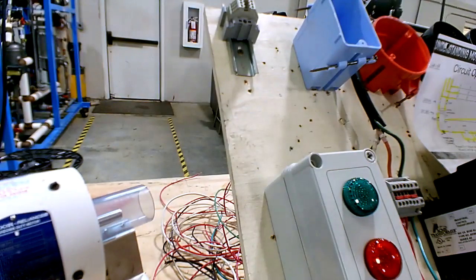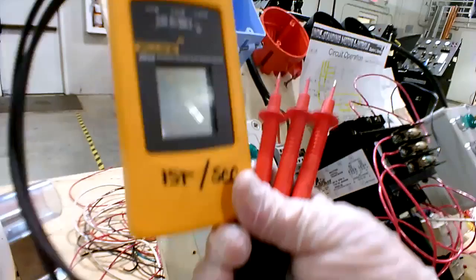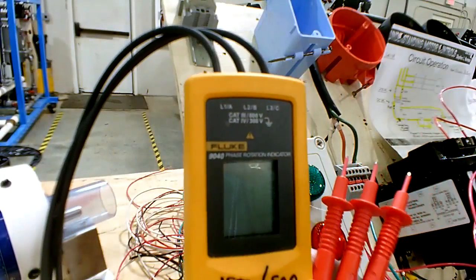Now, here's something for when it's critical that the motor goes the correct direction the first time and you don't want to just guess at it. If you've got something like a pump that would be damaged if you run it backwards when you hook it up for the first time, then you use something called a phase rotation indicator. This meter will actually tell you which way the motor is going to turn before you even start it.